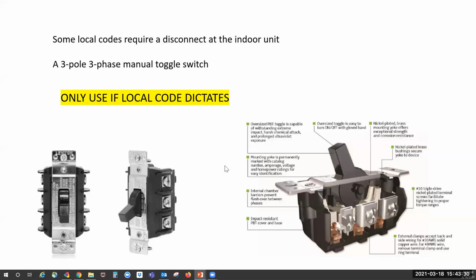If you have to use this for local codes, this is what you'd use. It'd be a 3-pole, 3-phase manual toggle switch, and you would run it where you got L1, L2, and L3 going through there and coming out. If you do not need this per code, do not use it. It's just another place where something can go wrong. So only use it if you must.